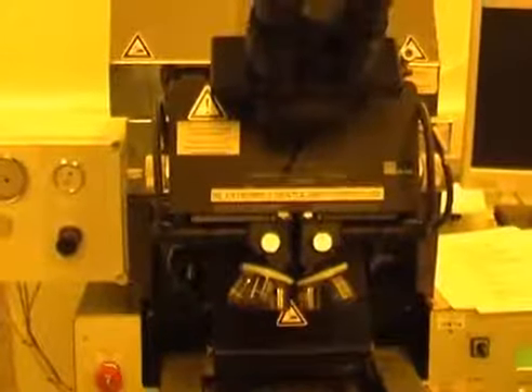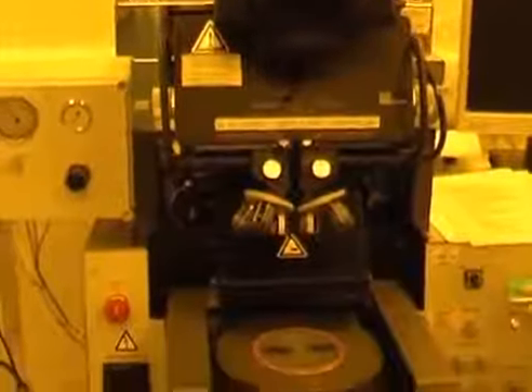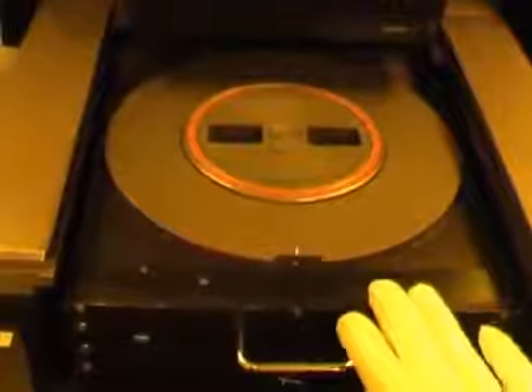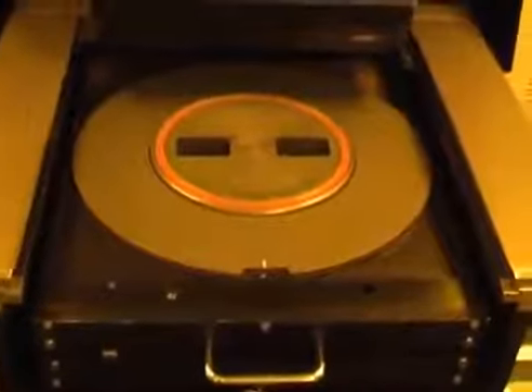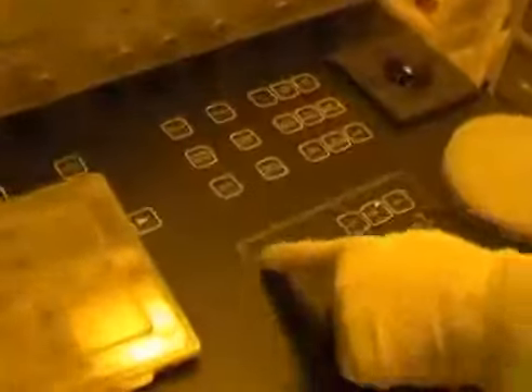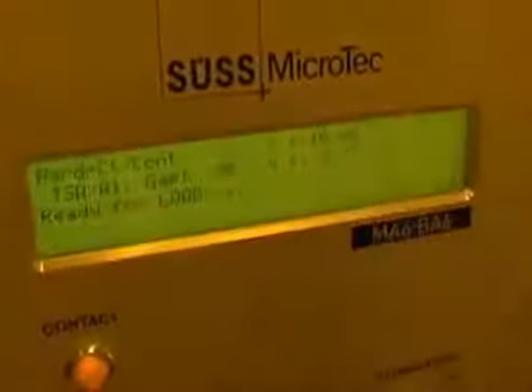Now, by default, the machine sets itself for backside alignment. The MA6 can do top side alignment and backside alignment, which means that the wafer is aligned from the back side of the wafer, not the top side. Most people tend to do top side alignment. Now all the keys for backside alignment are in this little box here. To deactivate the backside alignment, we press the backside alignment microscope key, and the instruction now changes to top side alignment.